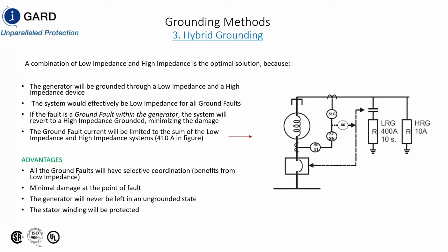Thank you, Sergio. So the next one is, does I-Gard offer engineering services to assist with preparing calculations and sizing equipment for hybrid grounding of generators? Yes, that was the easiest question to answer. Okay. What we need to do though is, if you give us a single line diagram and a cable schedule, we can probably determine what the capacitive charging current is of your system, and then look at your protection scheme and see what the minimum pickup is for ground faults, and then size everything accordingly. And unfortunately, we need to know the method of operation.